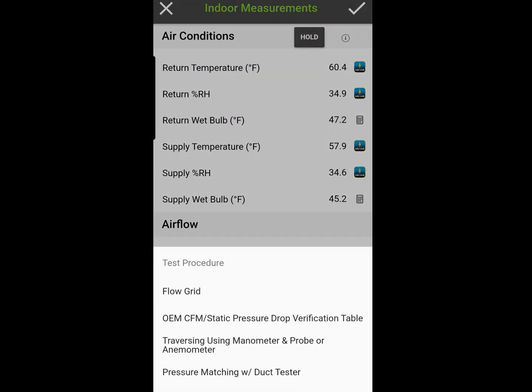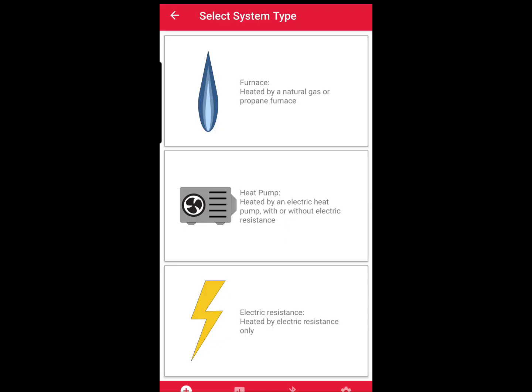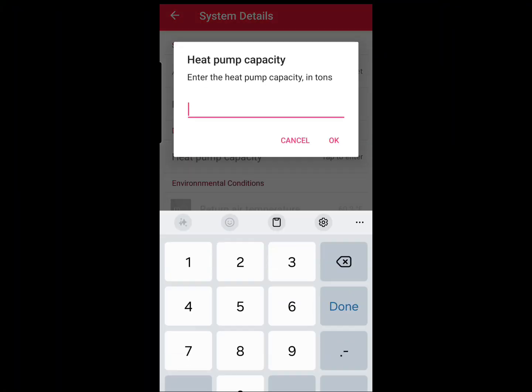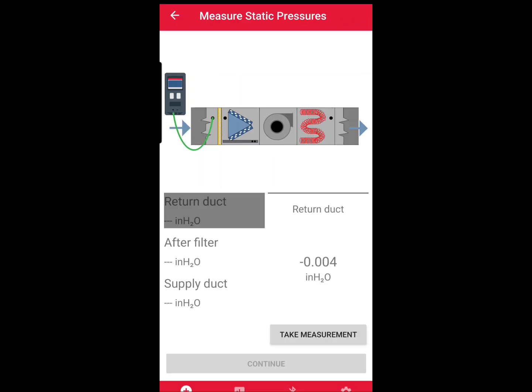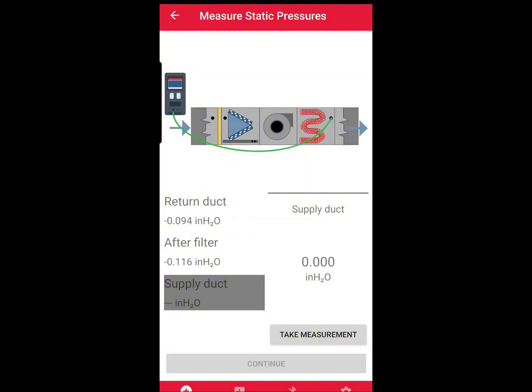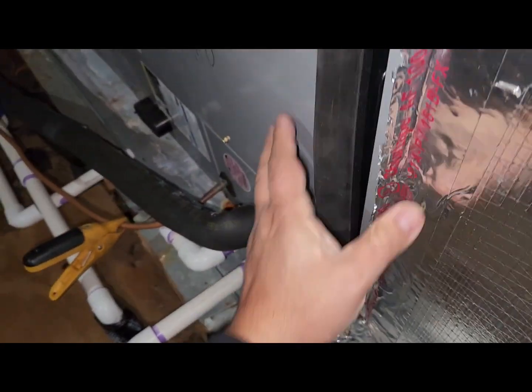The next thing I need to do is document the airflow. For that I'm going to use the TruFlow Grid by the Energy Conservatory — it has a MeasureQuick integration. We open the app through MeasureQuick and connect our devices. We tell the TruFlow Grid we're testing in heating mode, that it's a heat pump and not a furnace, that it's a horizontal air handler, where the filter goes, and the nominal capacity — three and a half tons. The TruFlow Grid app steps us through static pressure mapping. Eventually we insert the grid itself into the filter slot in the air handler so it can measure static pressure with the grid in versus with it out.